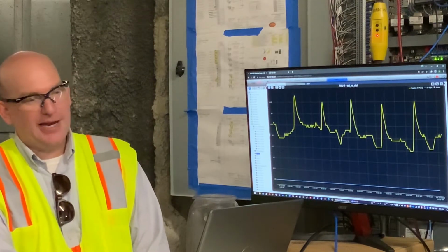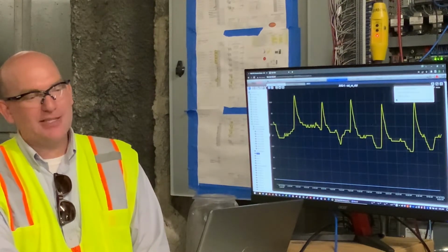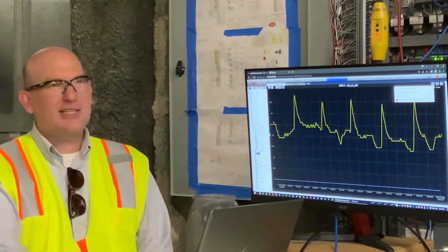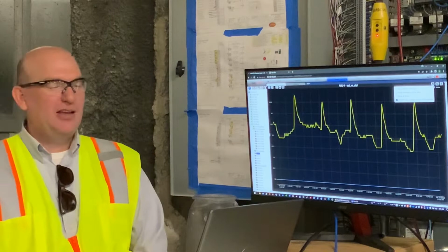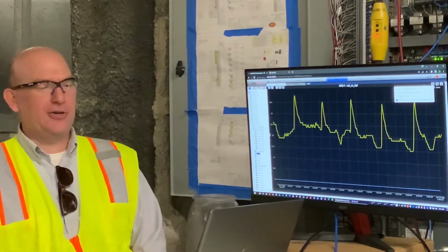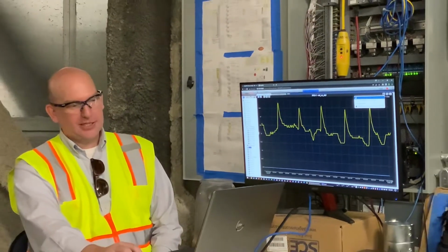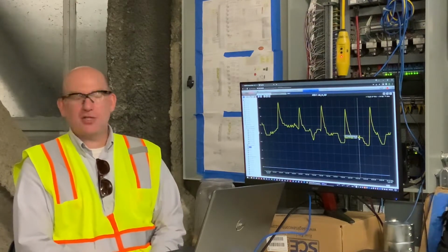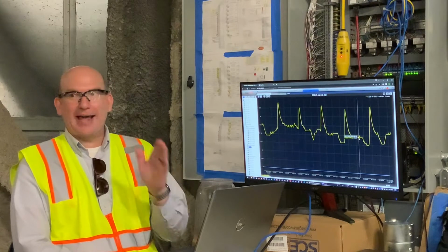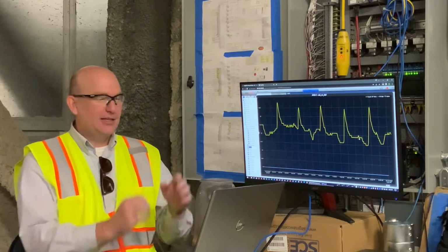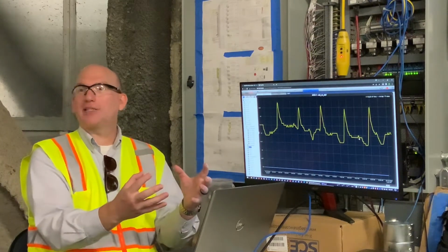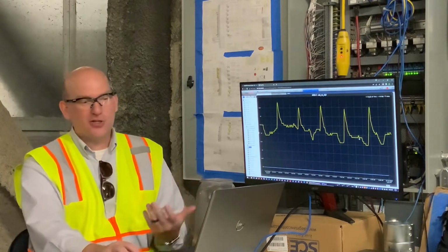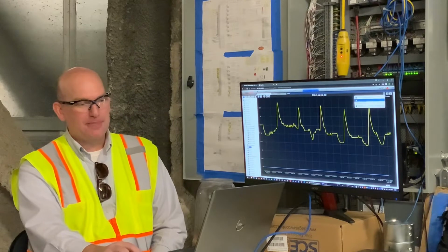On the other side, this is where you can set some different parameters for how you view the trends in the field. So now let's say you have a problem piece of equipment and you want to actively watch it while you're sitting at your desk. If you click this option here to auto update from the field, now every time a new trend sample comes in, while this screen is up, it'll add it in. Without that checked, it populates what you had at the time you populated it, and it waits until you refresh it to show you anything new. So it's basically like an active refresh.